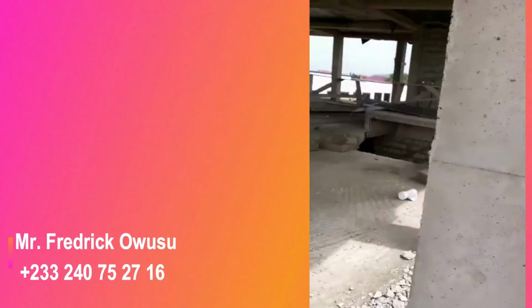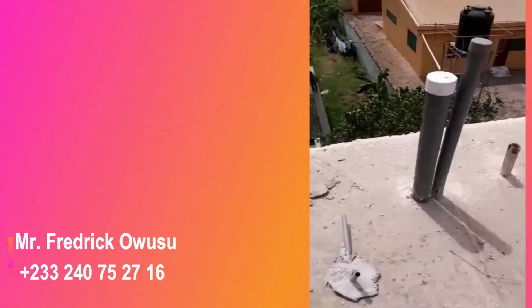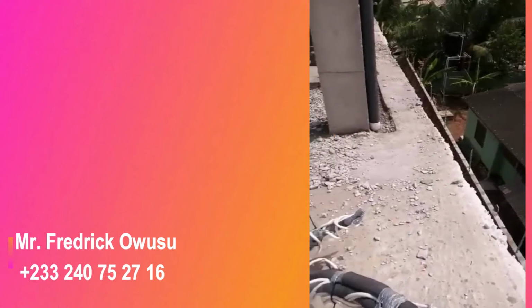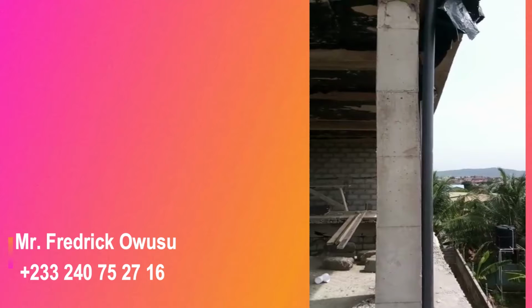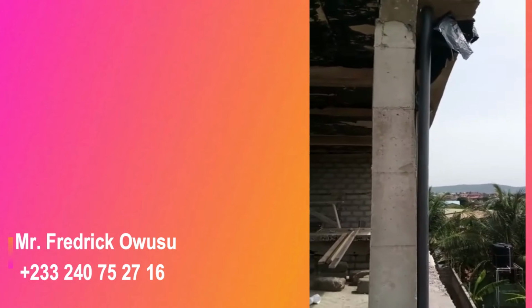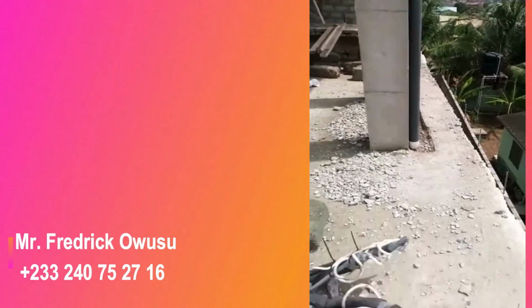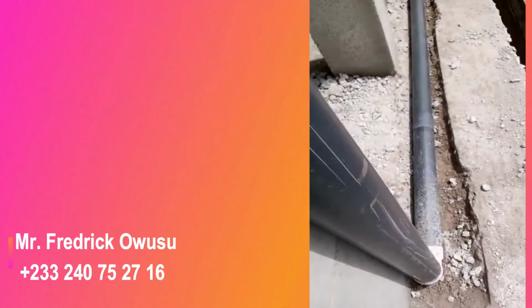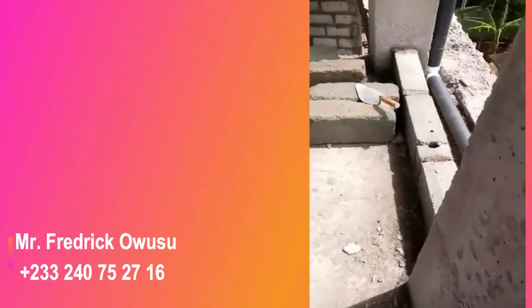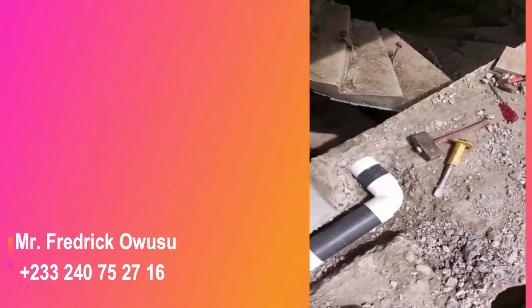And then when your house is ready, commissioned, and you are living there, you flush and the water is not going. You brush your teeth and wash the basin and you expect the water to flush away, but the water is going slowly. So kindly inform all your artisans that when you are at the site and there's an exposed and open pipe, let them use cement paper, a thick one, to cover the head of the pipe. Or your plumber should provide an end cap to all the piping so that it avoids any unwanted particles entering the pipe, because you can never see them. You understand? You can never see them.